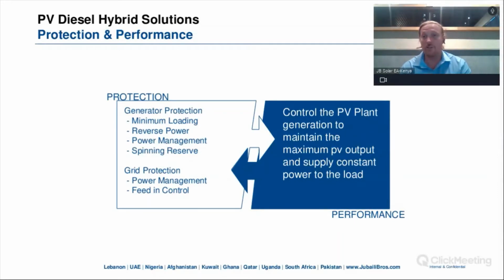Number 2 is reverse power. So this means that power cannot go backwards into the generator. So that's what the fuel save controller does. It protects the generator from reverse power flow. Number 4 is power management. That's really to do with the power quality and the active power and reactive power. And spinning reserve also. And I'll explain that in more detail, but it basically is a backup in case of high fluctuations on the load.